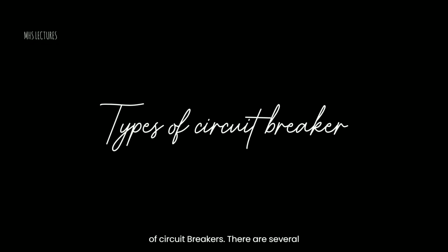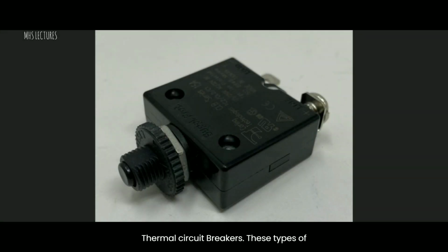2. Types of circuit breakers. There are several types of circuit breakers, including thermal circuit breakers. These types of circuit breakers use a bimetallic strip or a thermal element that bends or deforms when exposed to excessive heat caused by an overload. This deformation triggers the tripping mechanism, opening the circuit.